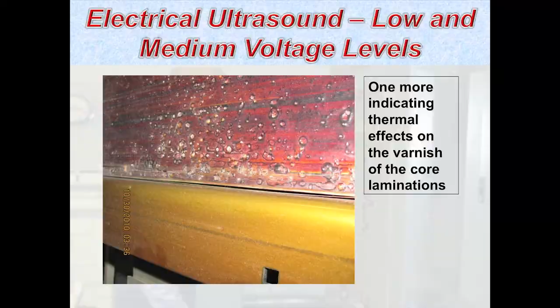Looking at the top of the core, the evidence of what's happening with the heating effects is even more evident on the varnish. When this stuff bubbles up and bursts, it's higher than normal temperatures. You don't want to see this on the core varnish. That was completely encapsulating the entire core on this unit at 5 years old.